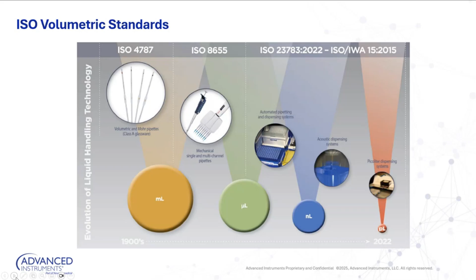Next slide, please. And then we have this nice little table that shows you where these standards originate from and the evolution. You can see volumetric glassware is under ISO 4787, but more so for the purposes of this audience, both piston operated single and multi-channel pipettes are under ISO 8655, and automated liquid handlers that are acoustic or positive displacement or air displacement are under ISO 23783. There are a couple other standards for those specifically as well, but those are how you calibrate and verify. Remember, ISO 8655 for manual piston operated pipettes, and ISO 23783 for automated liquid handling. Next slide, please.